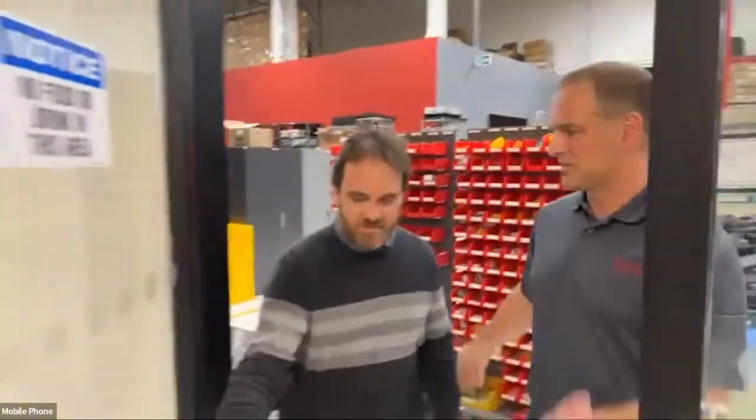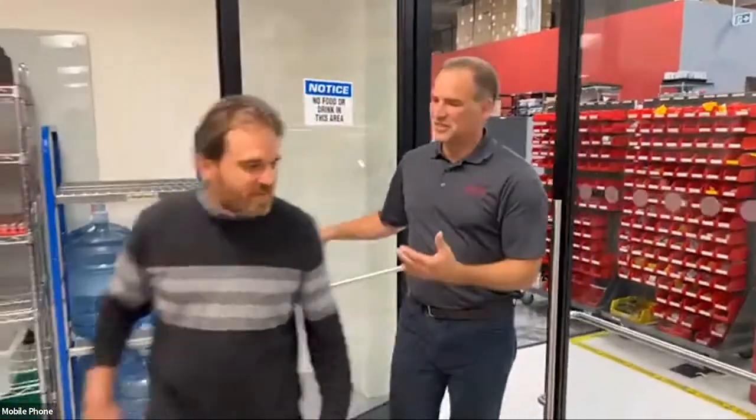So now we're going to the calibration lab where all the instruments actually get put through. Yeah, we put all the instruments through here. 100% of the instruments go through the calibration. That includes production units, service units, repair units, anything that comes through the door actually goes through the entire process. Excellent. Okay, so what parts of the process are we going to see? Since we're talking about a CTD, we'll be looking today at temperature calibration, pressure calibration, and conductivity calibration. Perfect, all three main areas of the instrument.